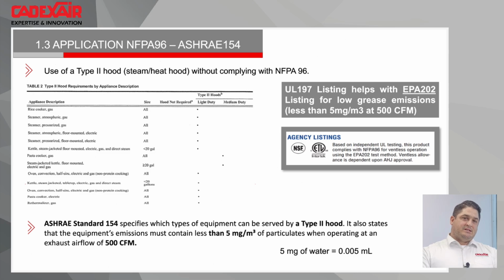So just to come back to the Type 2 hood, a Type 2 hood is for vapor and everything, and there's something in the ASHRAE 154 that says that if your kitchen equipment has more than 5 milligrams of grease per cubic meter at a 500 CFM airflow, you will need to have a Type 1 hood. If you're under, you can use a Type 2 hood. And I will say, what is this? What is 5 milligrams? What does it look like? I have zero idea about it.